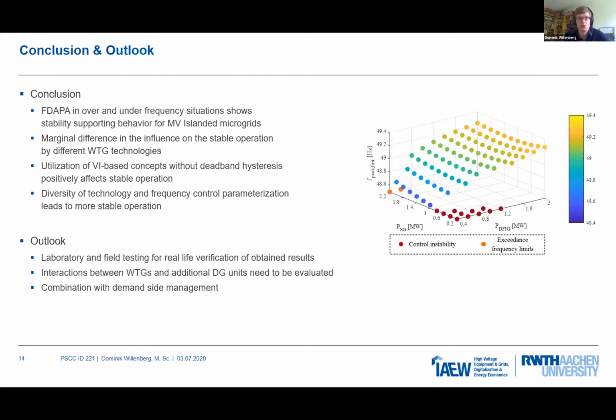So to conclude, the FDAPA in over and under frequency situations shows a stability supporting behavior. There's only a marginal difference between different WTG technologies, and the diversity of technology and frequency control parameterization leads to a more stable operation. As an outlook, since all the results were performed in simulations, a laboratory or field testing for real-life verification is necessary.